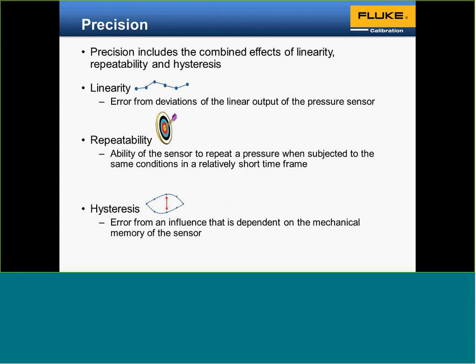Precision, and it includes the following bullets: linearity, repeatability, and hysteresis. Nonlinearity, or linearity as it's commonly called, is the error from the deviations of the linear output of the pressure sensor. We take a single pressure point along the span of the sensor, and in those points we hope they're linear, but there are some linearizations in the linearity specification.